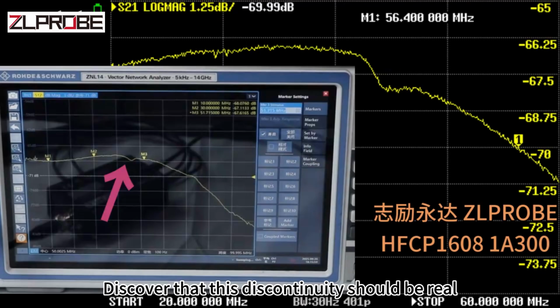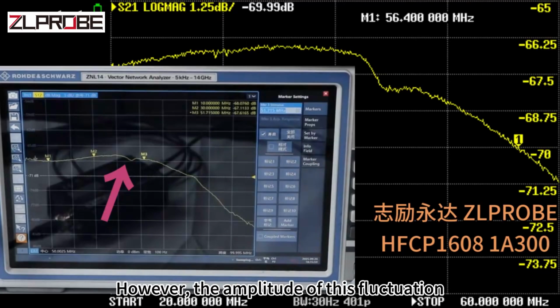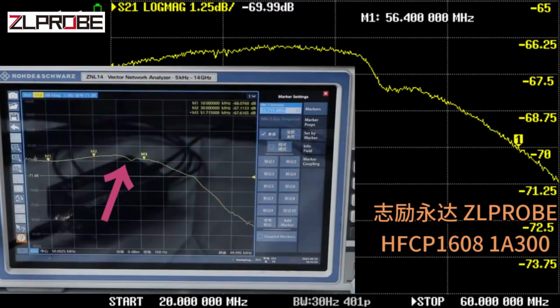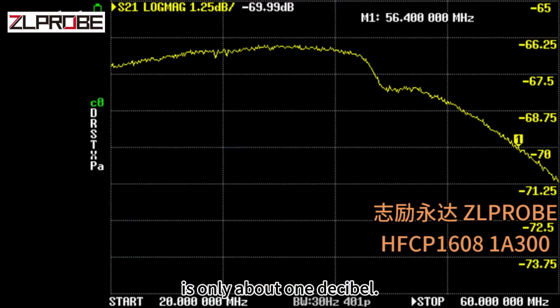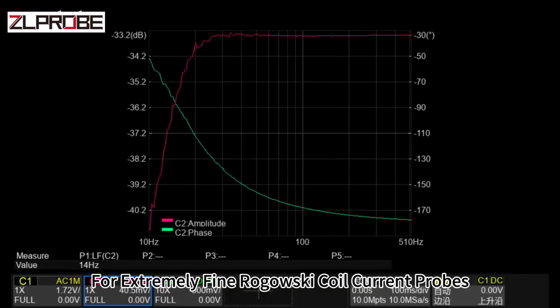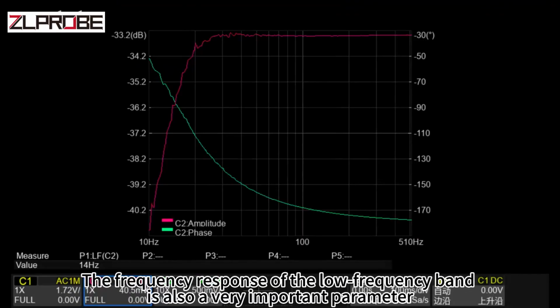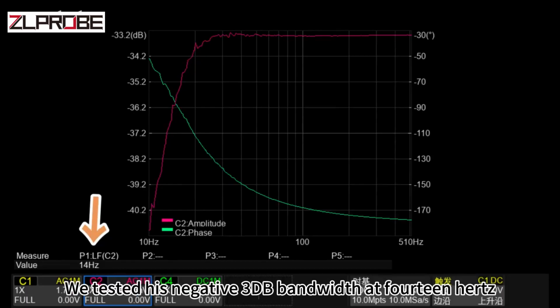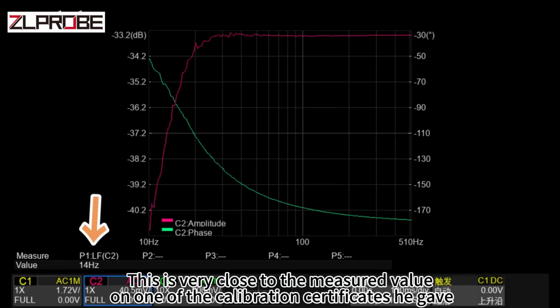Discover that this discontinuity should be real. However, the amplitude of this fluctuation is only about 1 dB, so it's not really a problem for extremely fine Rogowski coil current probes. The frequency response at the low-frequency band is also a very important parameter. We tested its -3 dB bandwidth at 14 Hz.